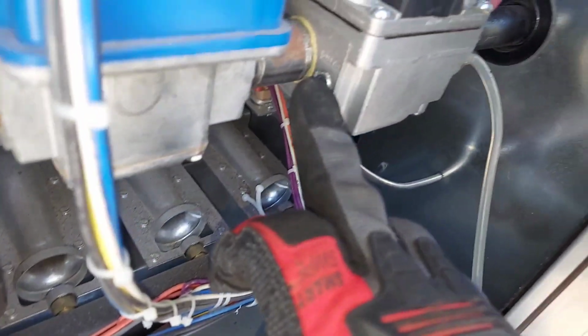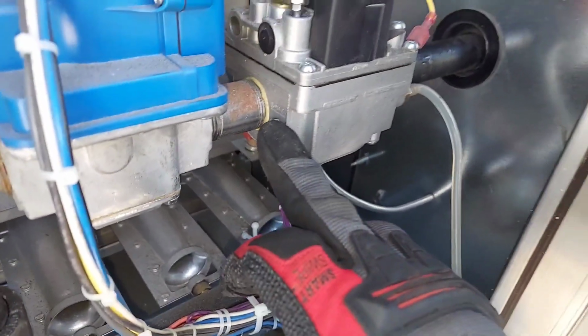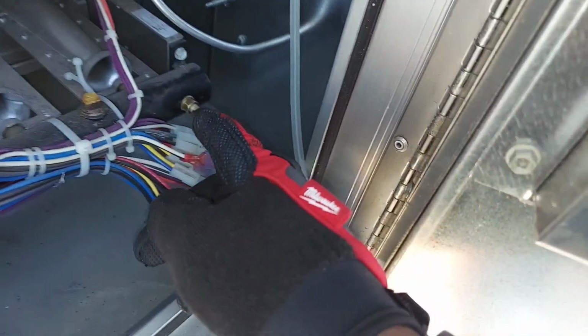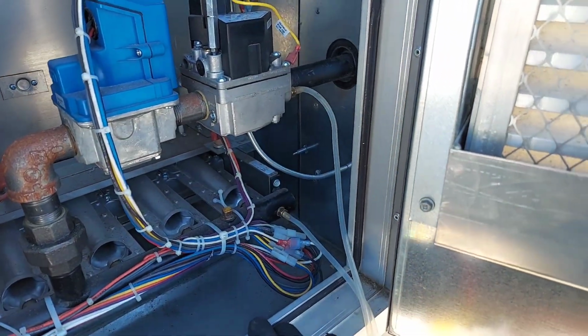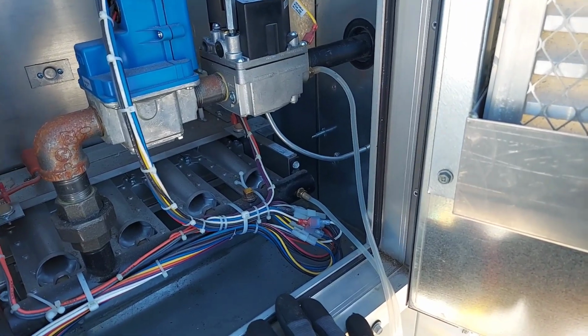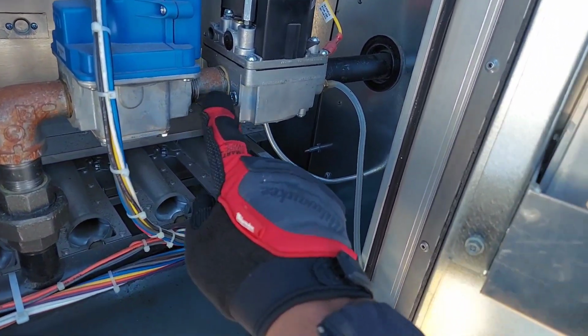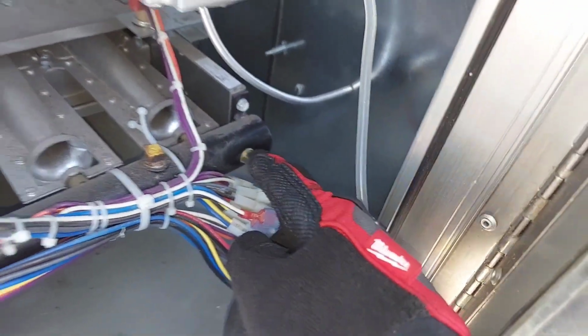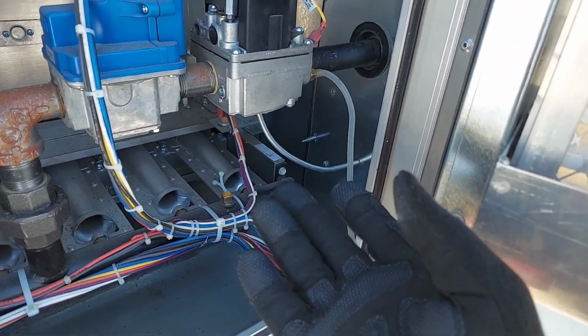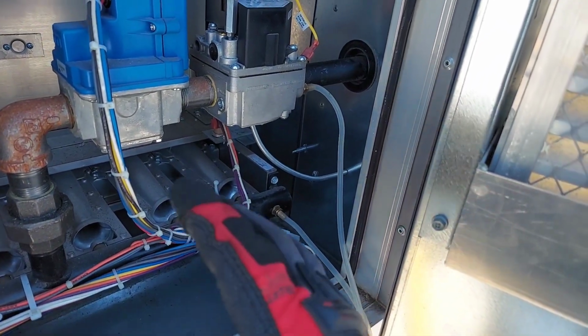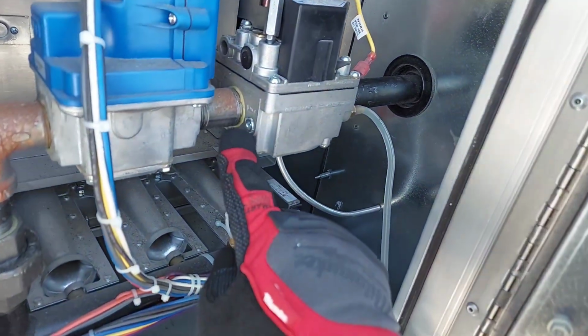Now, also right here, that's the outlet. But I prefer to go down in the manifold to get my pressure readings. But you could go right here as well, if you don't have any taps on your manifolds, which is almost never the case. There's always going to be a tap on your manifold, but you could go right here.